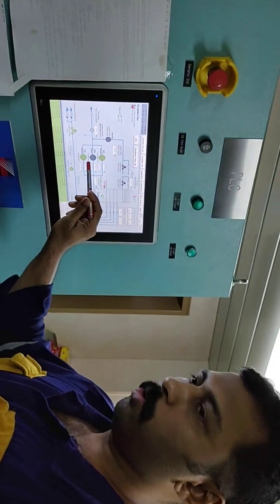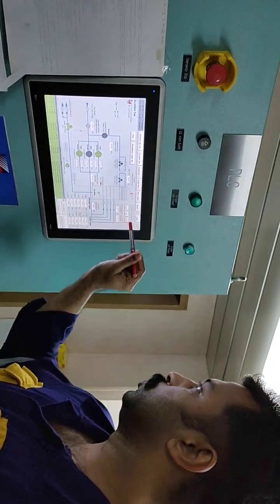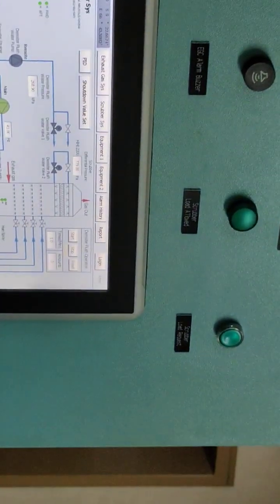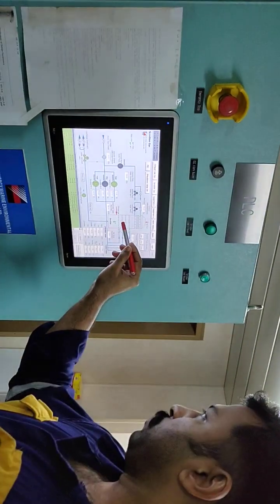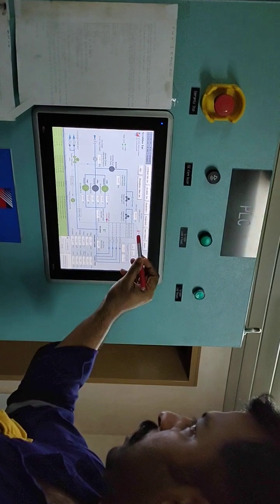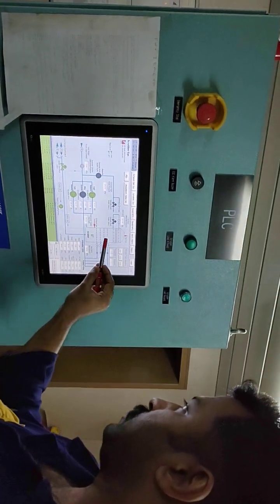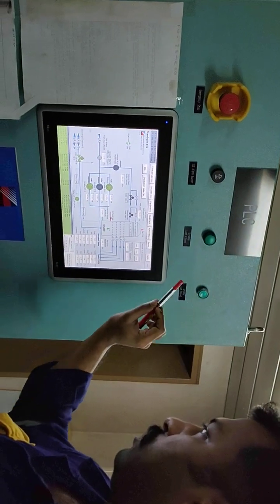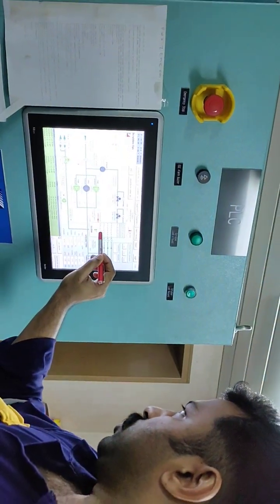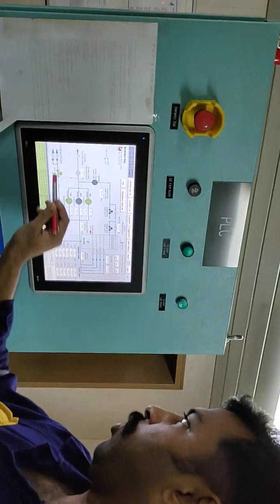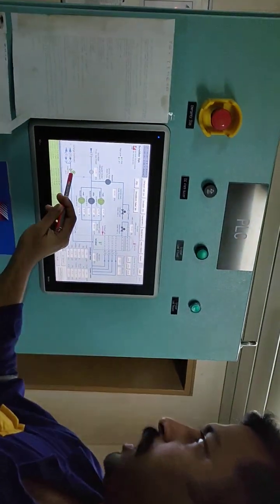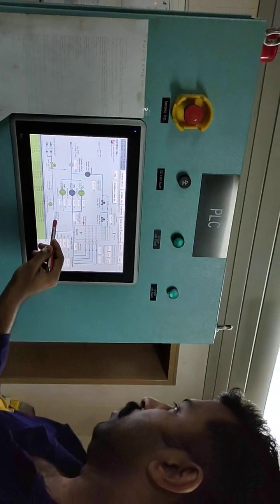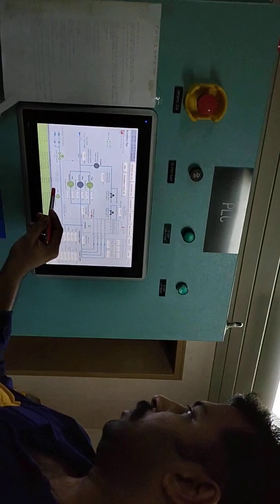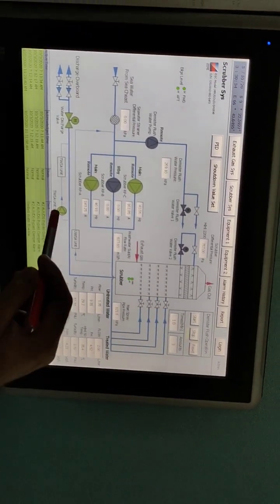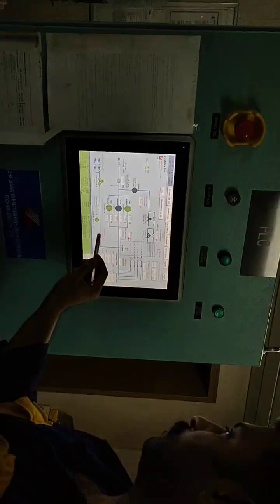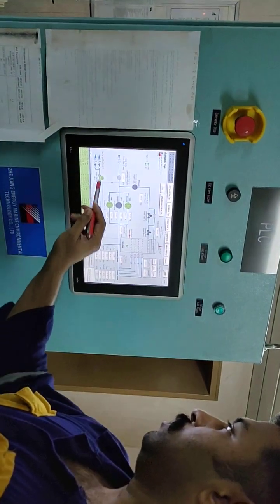You can change which pump you want to run and which pump you want to put in standby. You can choose from the equipment list. I will tell you later. Now this pump supplies water to the scrubber unit, and the water gets sprayed inside the scrubber tower and all the uptake gases get cleaned and go out. That's all. And this water by gravity normally keeps on going overboard. It has a water discharge valve. This is automatically operated. From the overboard line, we have a treated water sampling analysis unit with a pump, which is a diaphragm pump, which also has a display unit, directly to overboard.